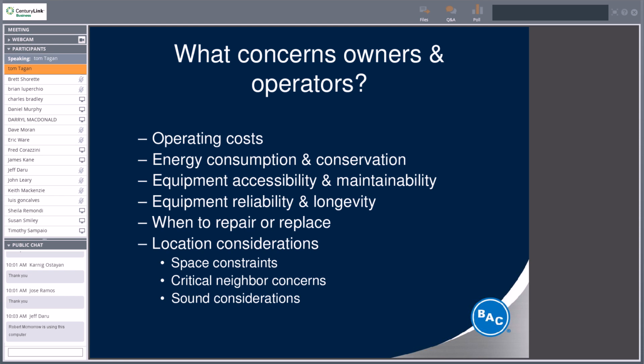What concerns do the owners and operators have? In the middle of it, when you're trying to keep your building up and going, you're worried about maintainability, but your owner's worried about the operating cost and then the energy consumption. So everything you do, especially keeping the cooling tower clean and operating effectively, does address the bottom line. Location considerations, as we talked about, if you're on the ocean, you may find yourself replacing components more often than if you were in the middle of Central Mass. But that's usually taken into account. I know most engineers really spend a lot of time in the early design on making sure that the materials they put in are going to last as long as possible.